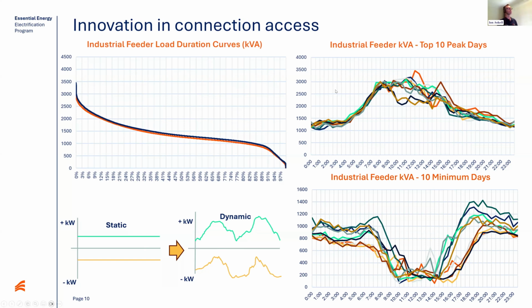So in this example, this is an industrial feeder linked to an industrial precinct, where we already have a load duration curve, experiencing about 3.5 megawatts peak demand on the network. But outside of that time period, there's a significant amount of asset capacity that can be utilised. So we're currently working on developing a trial to signal that spare capacity on a real-time basis for an eTES unit to soak up.